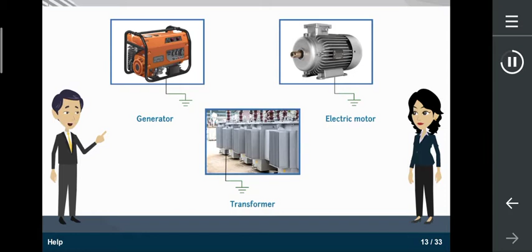Apart from these, the frame of every generator, stationary motor, and as far as practicable, the portable motor and the metallic parts of transformer and any other apparatus used for regulating and controlling energy and all medium and high voltage energy consuming apparatus should be connected by two separate and distinct connections with earth.